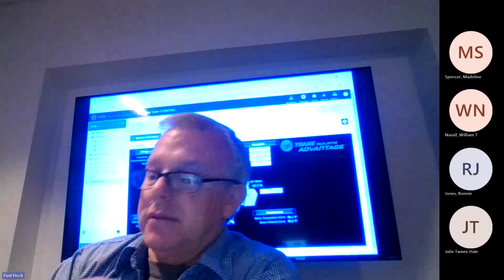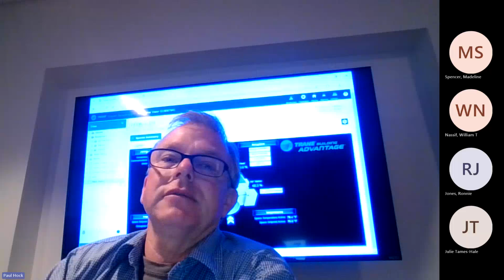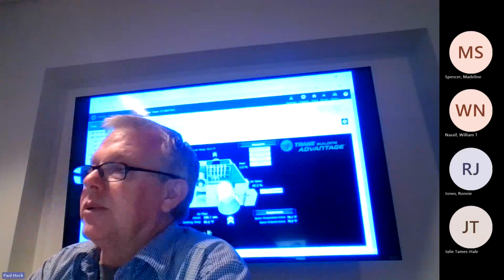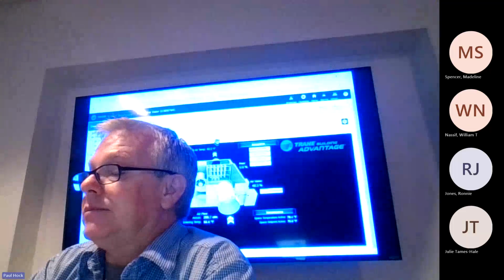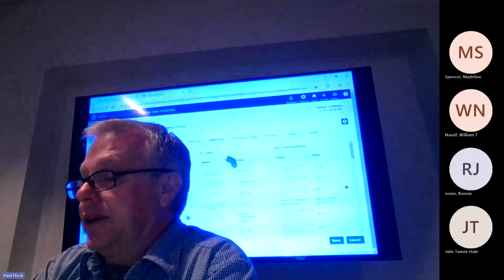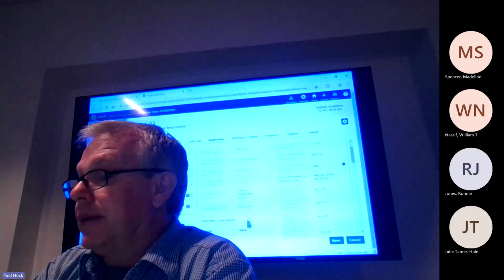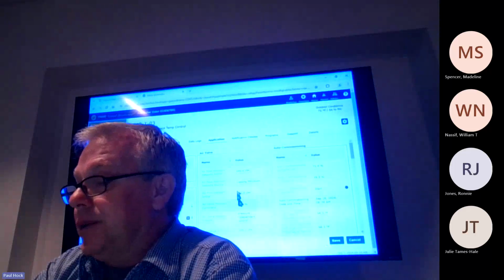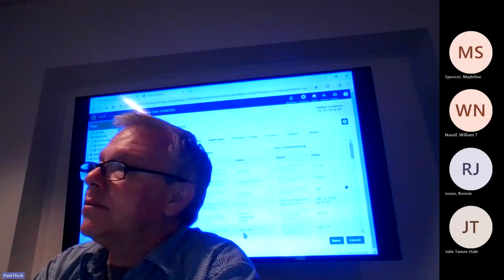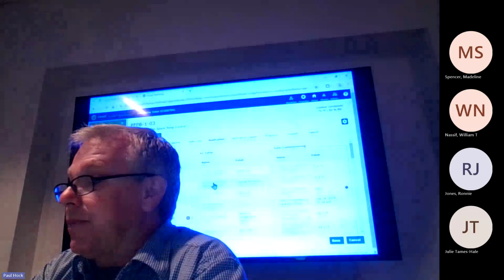Can you add airflow set point to the graphics? And I'll get that done too. That way you guys know what it's acting for. There's the applications tab right here. This first box, air valve, is to tell you what it's looking for. Right now it's looking for 200 CFM, putting out 205. You'll see that fluctuate a little bit. It tells you where it's coming from.